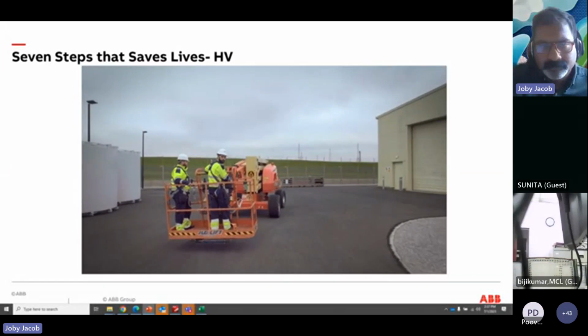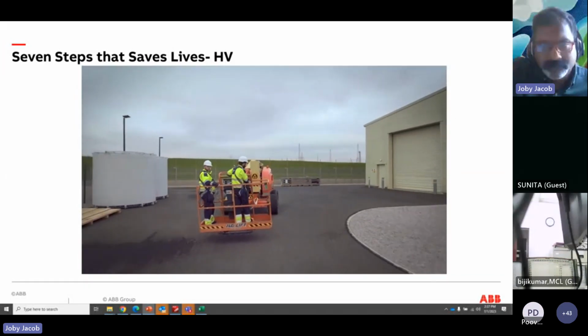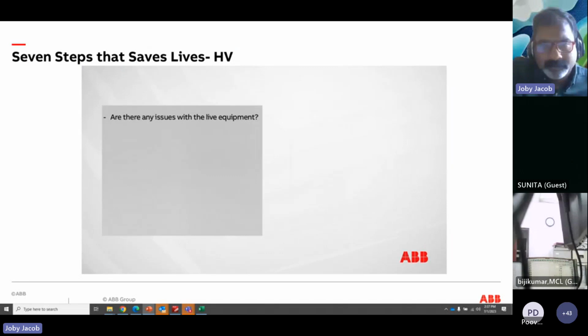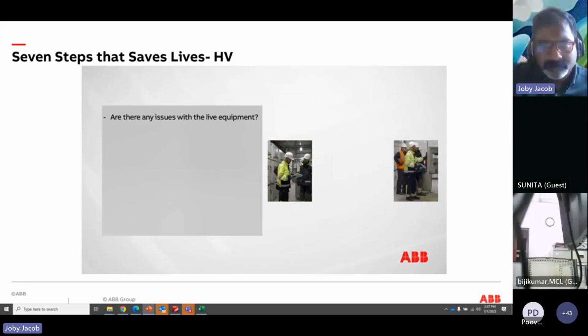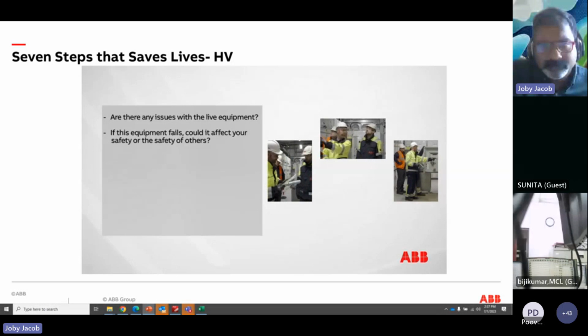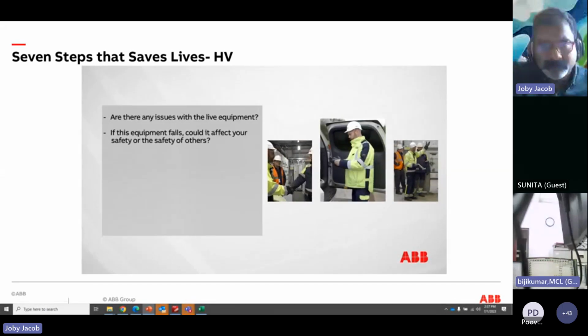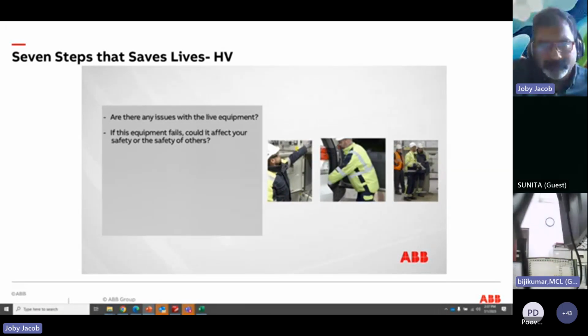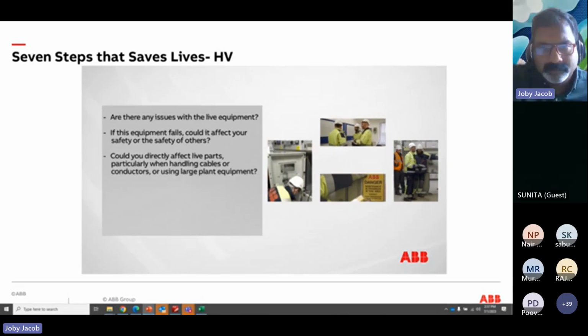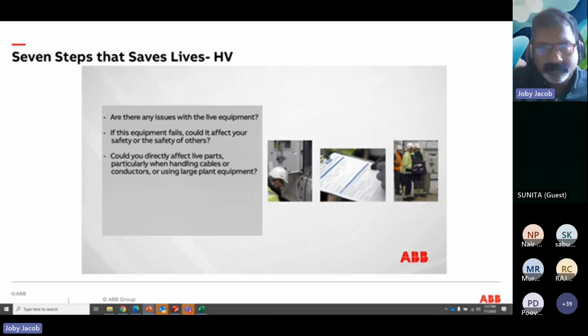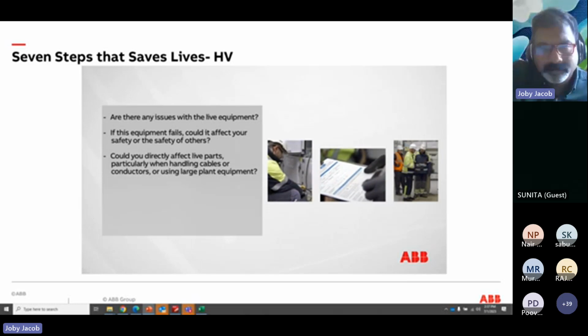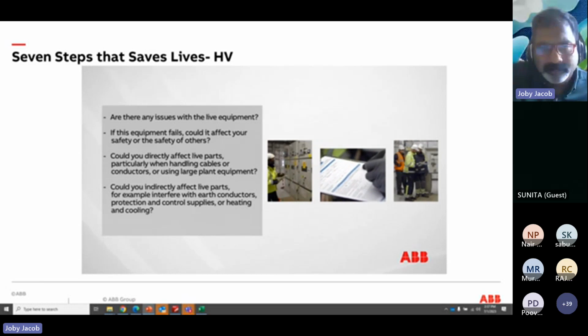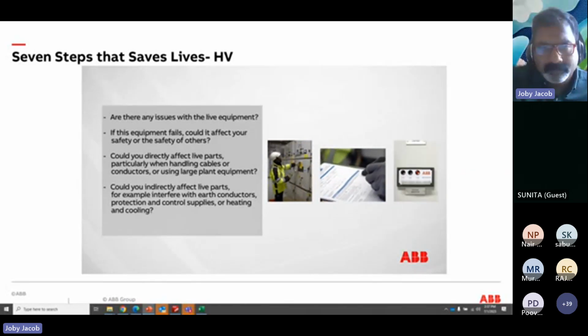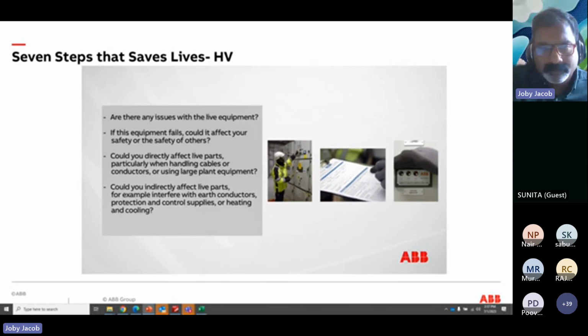Continue to reassess the risks, asking yourself these questions. Are there any issues with the live equipment? If this equipment fails, could it affect your safety or the safety of others? Could you directly affect live parts, particularly when handling cables or conductors or using large plant equipment? Could you indirectly affect live parts, for example, interfere with earth conductors, protection and control supplies, or heating and cooling?